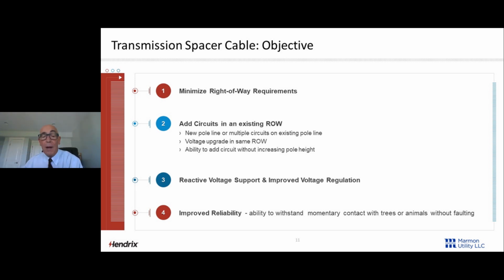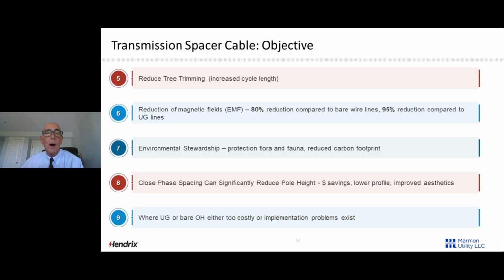We're going to have improved reliability, the ability to withstand momentary contact with trees and animals without faulting. We want to reduce tree trimming. We want to increase the tree trim cycle length. There's a benefit that's not talked about anymore. It was a big deal 20, 30 years ago: reduction of magnetic fields. We'll talk about that a little bit. 80% reduction compared to bare wire, 95% reduction compared to underground.